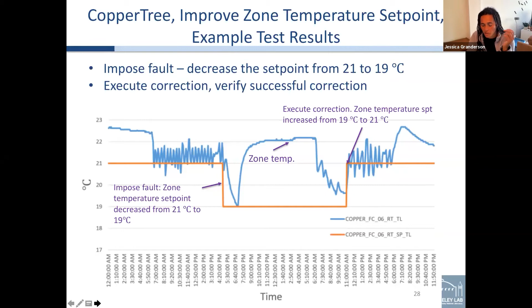The set point, a heating set point, is shown in orange, and the blue line is the actual zone temperature. At the start of the day that heating set point was at 19 C, and we want it to be 21 — we go in and correct it back to the appropriate value. You can see the zone temperature responding as well to those changes. So here's a way for us to draw data from the field, monitor what's happening, and prove that the system is behaving as intended.